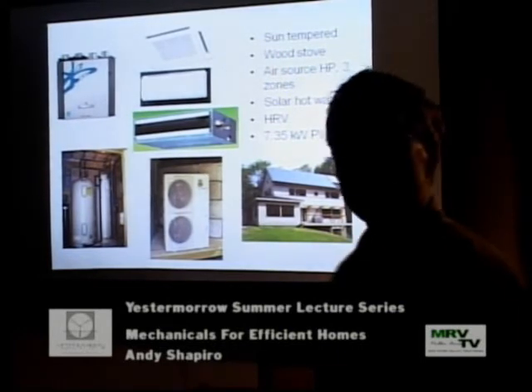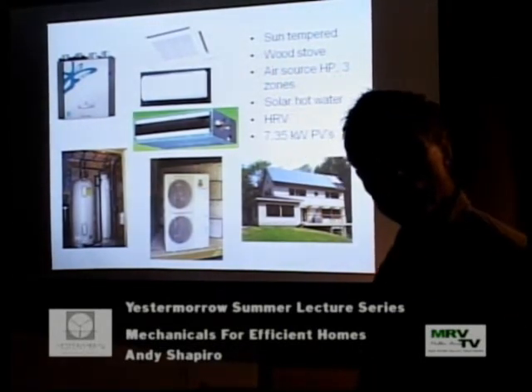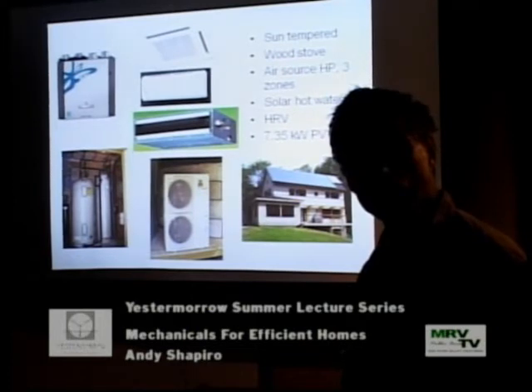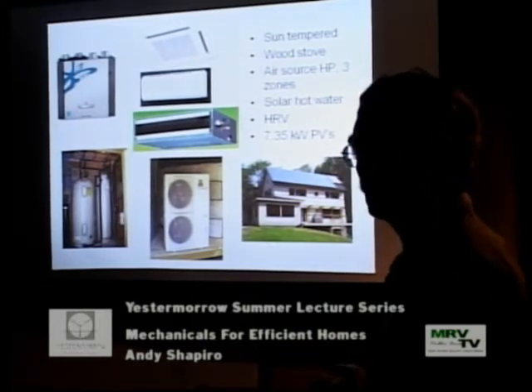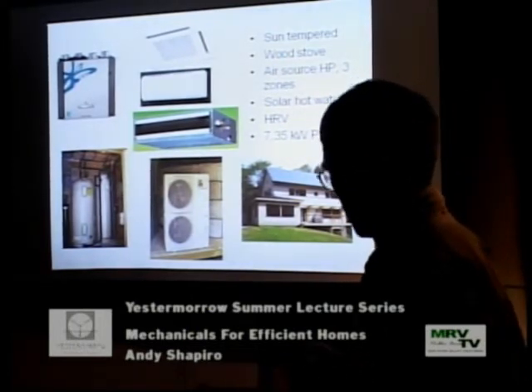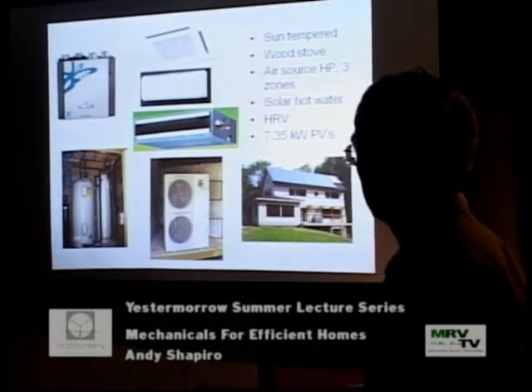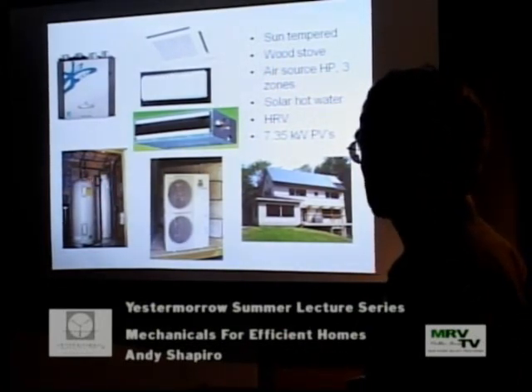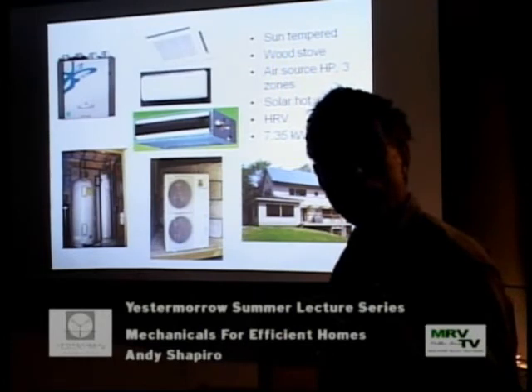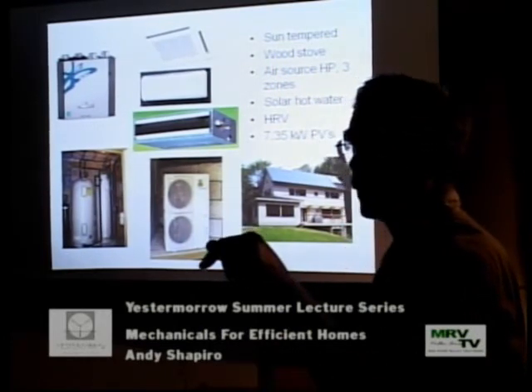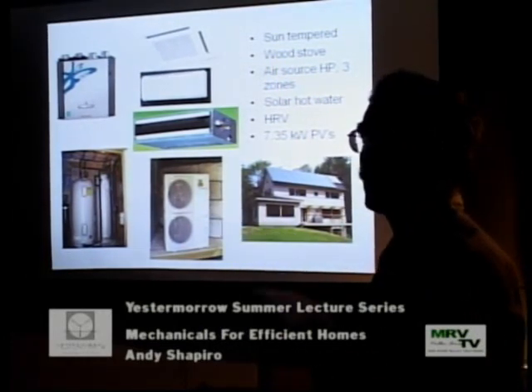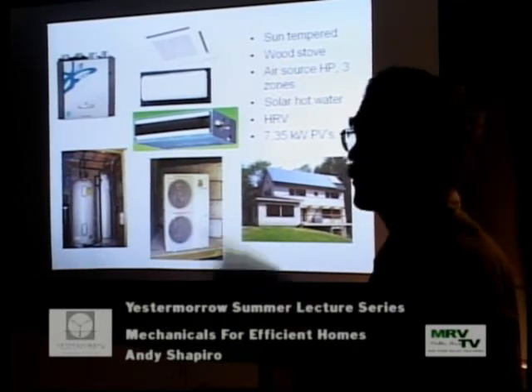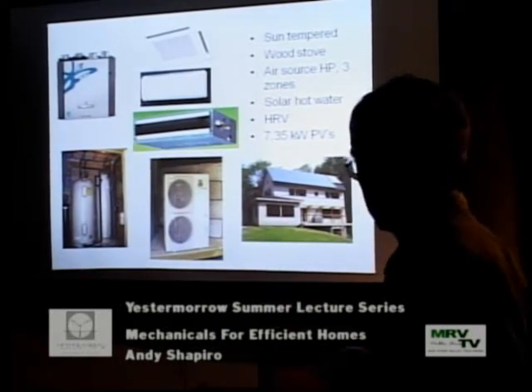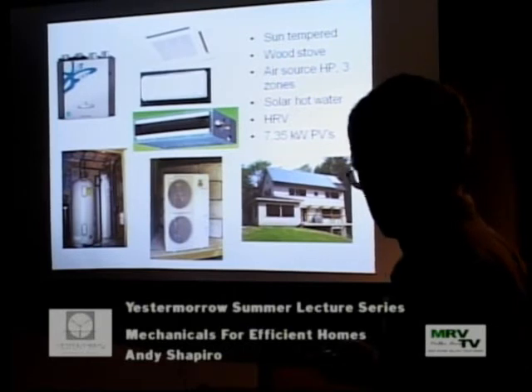If your solar hot water has an electric resistance backup in it, why do you need the Marathon too? A two-tank system's a little bit more efficient. You can set it up where there's a tiny little circulator between the two, so that when the solar tank gets hot - rather than having to wait to draw water to bring that into the tank - the circulator says the solar tank's hotter than the backup tank, dump some of the heat in there. So you can make up your standby losses with the solar that way, which is what we did.